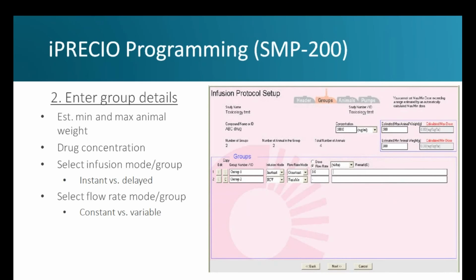The second window is where you enter the concentration of the solution, and the minimum and estimated maximum animal weight that is expected at the end of the study. The software will then automatically calculate the minimum and maximum dose, which can be administered during the experiment. You can also select an infusion mode and input the dose, or select a flow rate mode and enter the desired flow rates that you want to infuse.